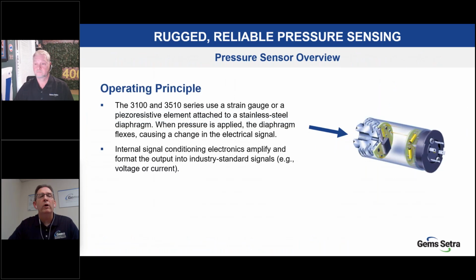So a little bit about how they work, and I'll keep it relatively brief. The two models, one using strain gauge, the other piezo resistive elements, are attached to a stainless steel diaphragm, and as pressure is applied, that diaphragm flexes and changes the electrical signal internally. That electrical signal is then interpreted by some onboard electronics to amplify it and put it into the output that we spoke of. Again, voltages, the current rating, or a ratiometric output. So as pressure changes, that output changes, but it is a continuous reading at all times.